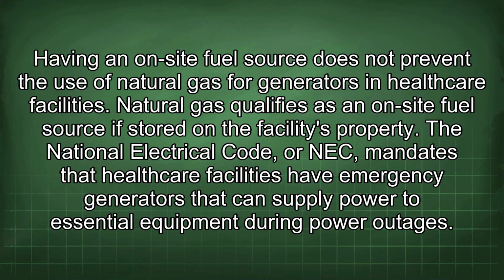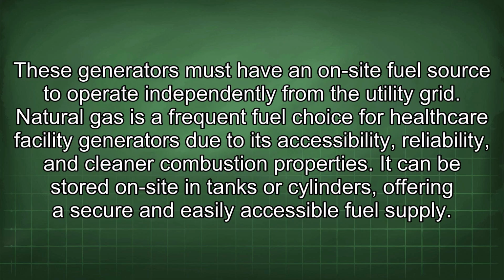Having an on-site fuel source does not prevent the use of natural gas for generators in healthcare facilities. Natural gas qualifies as an on-site fuel source if stored on the facility's property. The National Electrical Code, or NEC, mandates that healthcare facilities have emergency generators that can supply power to essential equipment during power outages. These generators must have an on-site fuel source to operate independently from the utility grid.